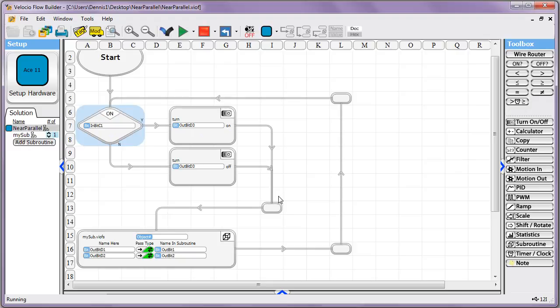And then the other important thing that we're doing here is I've got the whole program in one big loop, so that every time we're going to go through and do both of our operations, or you may have 6 or 12, you may have a whole lot of operations that you want to do, but you want to perform it all in one loop so that everything that you want done every scan is done every time.